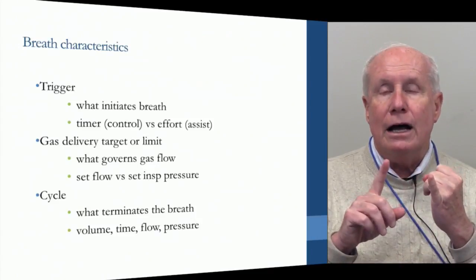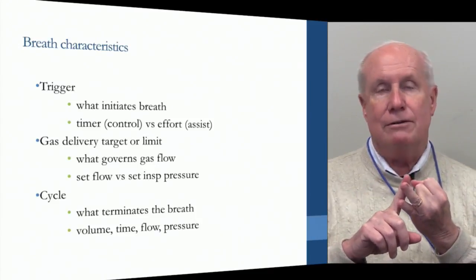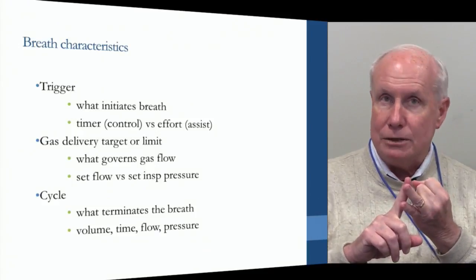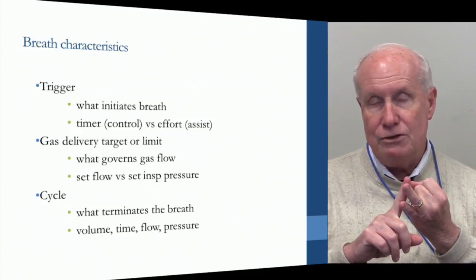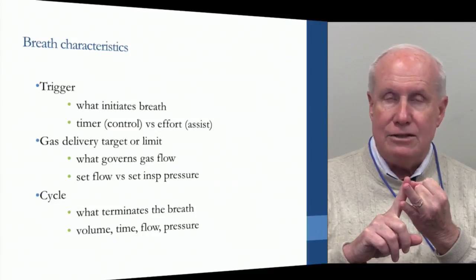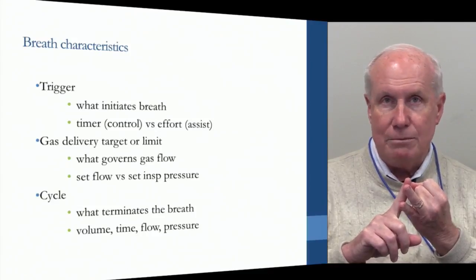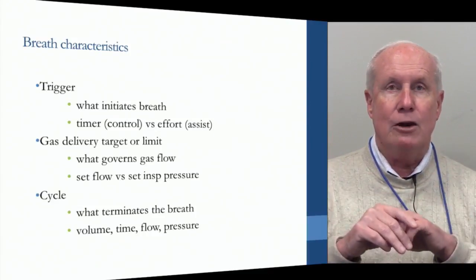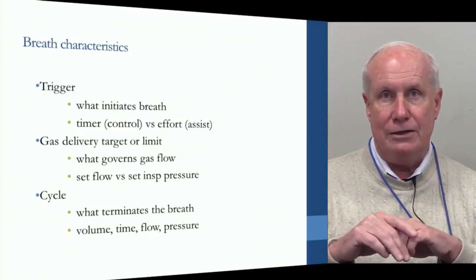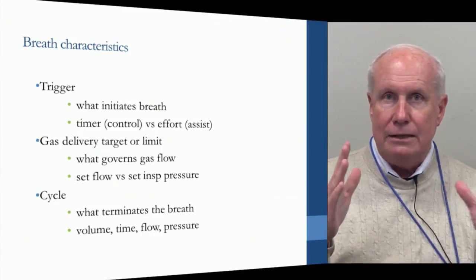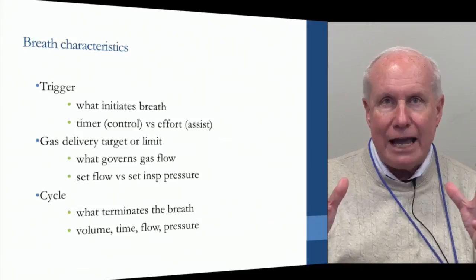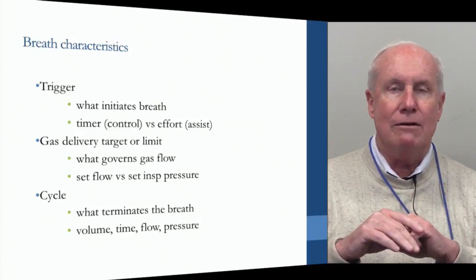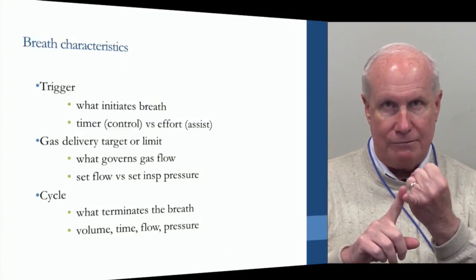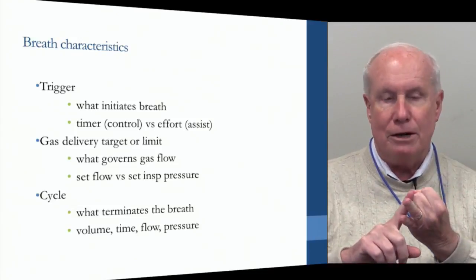And the other approach is to not set a flow, but to set a pressure. So you don't set a flow, you set a pressure. You set 10 centimeters of water, 20 centimeters, or 30 centimeters of water. And this is what the ventilator will deliver during the inspiratory phase. So they don't deliver different amounts of gas, but the way the gas is governed by the ventilator is different. One is a set flow, one is a set pressure.